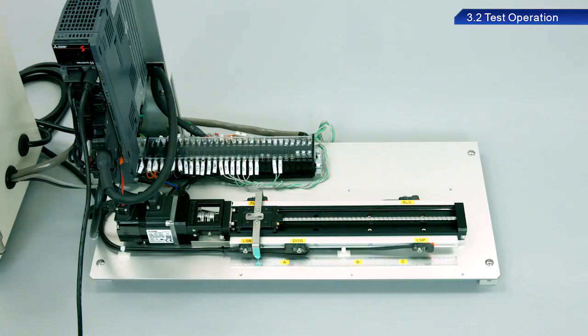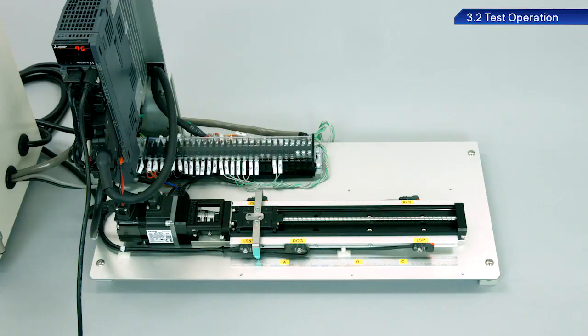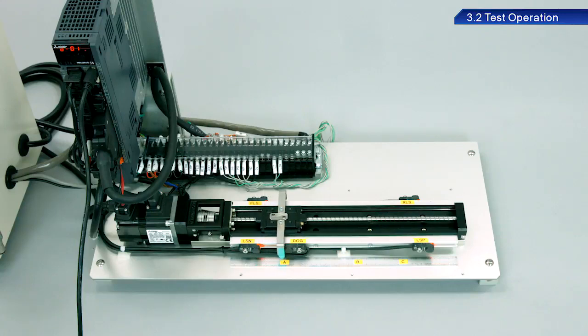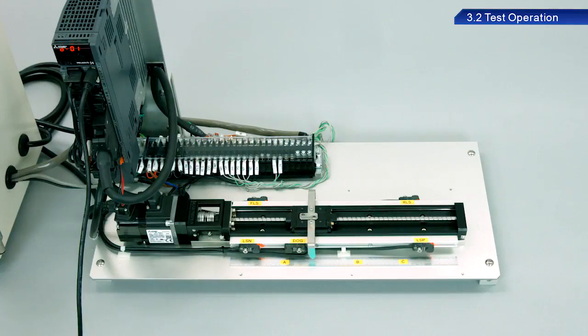Turn the power off and on again. The alarm is cleared by turning the power off and on. Then move the motor in the opposite direction from before the servo amplifier stopped. The motor should have moved again. Mechanical limits can be set in this way to ensure safety.